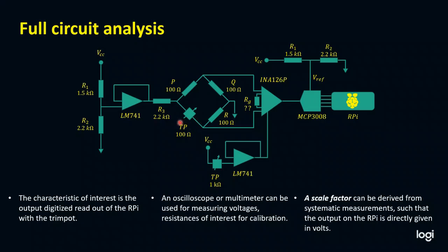One is you can either replace the TP 100 ohms with some fixed resistances so that you have a readout corresponding to some fixed resistances. Alternatively, you can also use a digital potentiometer here, and by scanning the digital potentiometer, you can then do an automated calibration of the whole interrogator circuit.